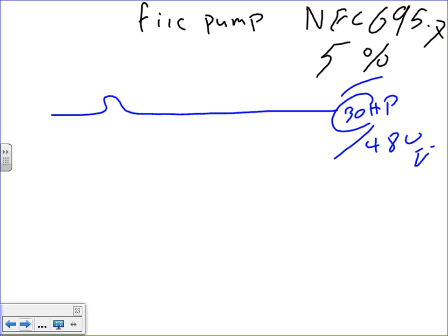Yeah, that's what I thought. That's okay. The starting capability 15%. The drop is 5%, right? That's good. Thank you. Yeah, it's a little bit confusing. 5% constant drop, 15% momentary drop or dip, they call it, for the start only.